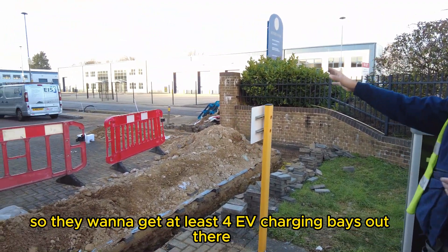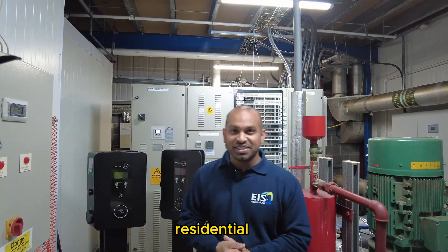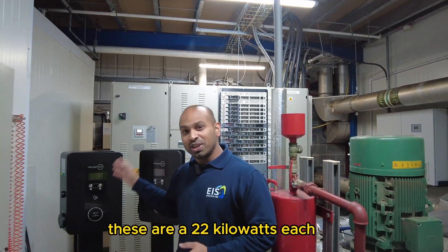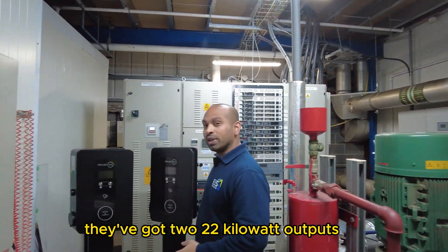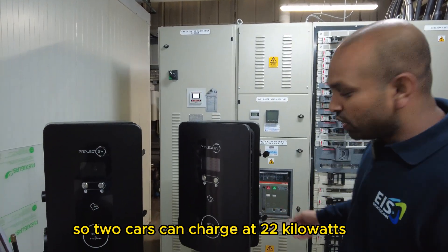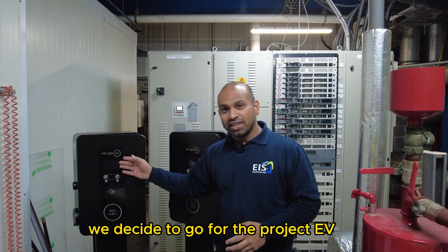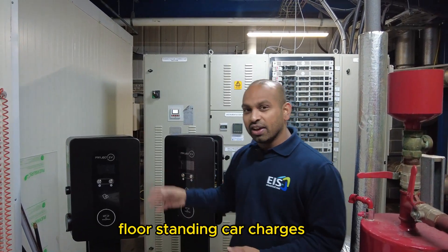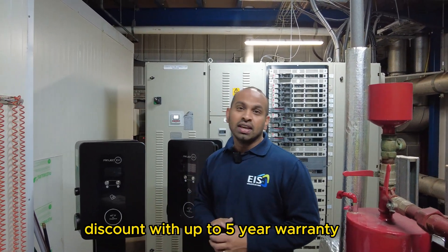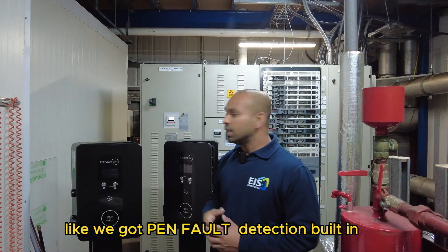They want at least four EV charging bays out there. These two units are not your regular residential 7-kilowatt chargers — these are 22 kilowatts each, with twin 22-kilowatt outputs, so two cars can charge at 22 kilowatts simultaneously from each one. We decided to go for the Project EV floor standing car chargers mainly because of their warranty — these come with up to a five-year warranty.